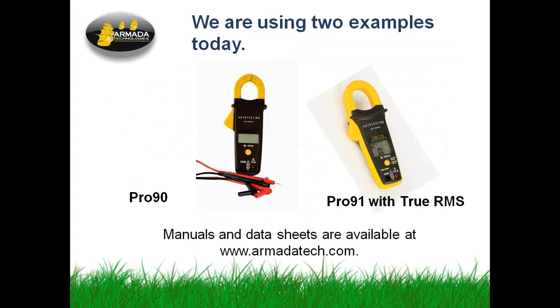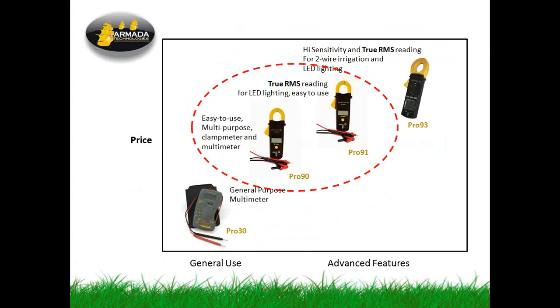So meters and the data sheets and information on these meters you can get from our armadatech.com website. So I'm not going to talk a lot about detailed specs, but just about applications and the nature of the specs. These two meters are in the middle of our line, as I said, and they're targeted for general purpose use in green systems, irrigation and lighting. The Pro91 in particular is targeted at lighting systems that are migrated to LED because there's a little different measuring technique required there. We have a fancier, more expensive meter that's very sensitive, that's used in two-wire irrigation systems and some lighting systems. That's on the top right, and the lower left is our inexpensive pocket meter, the Pro30, kind of a $20 item, but very useful for a lot of things you do, but some things clamp meters can't be replaced with.